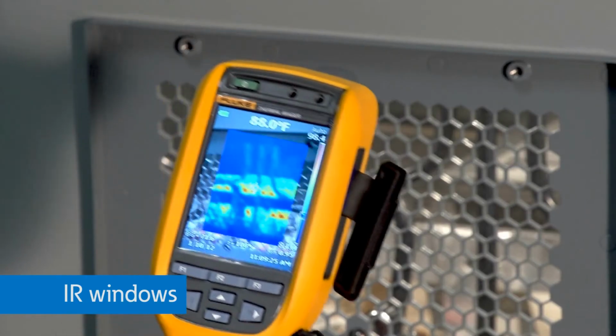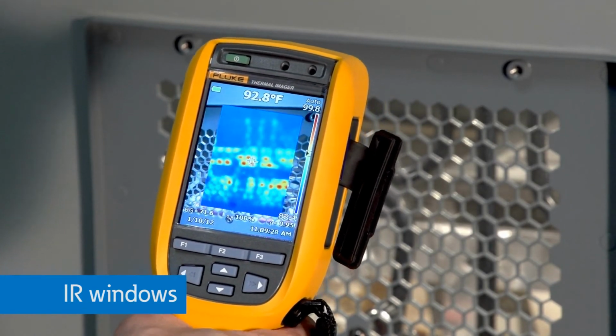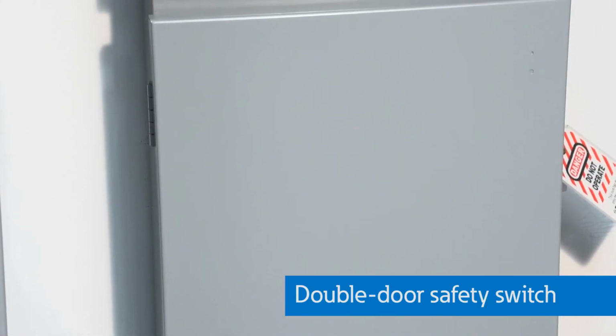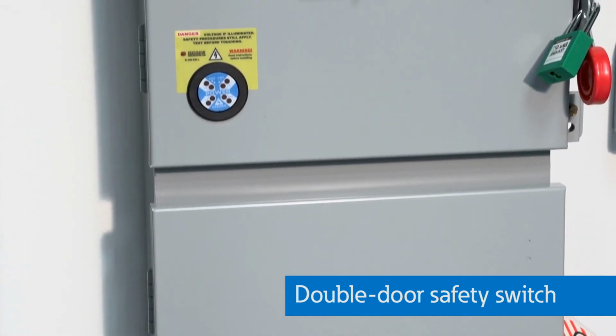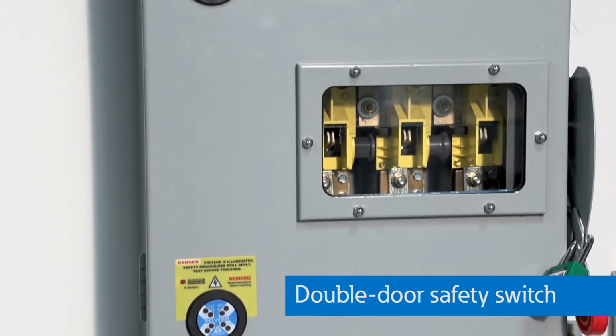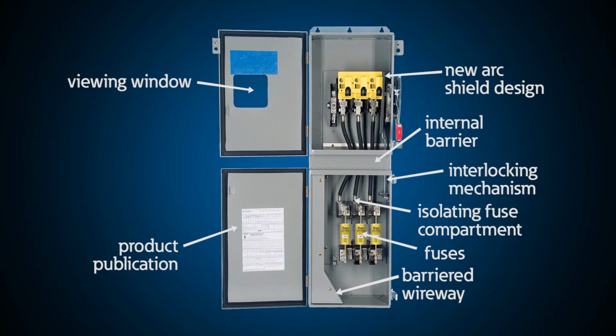Other arc flash safety solutions to keep you out of harm's way include IR windows that allow you to look for potential issues inside your switchgear, switchboards, or other equipment like busway. Double door safety switches allow you to install fuses and make connections on the load side of this switch without being exposed to the line side or energized connections. This greatly reduces risk, as you must consider the arc flash level on the source side even if the switch is in the open position with the door open on a standard safety switch. Anything that compartmentalizes electrical components generally helps with arc flash.